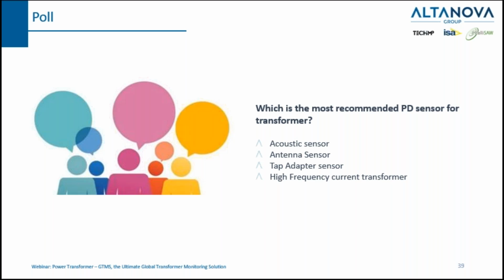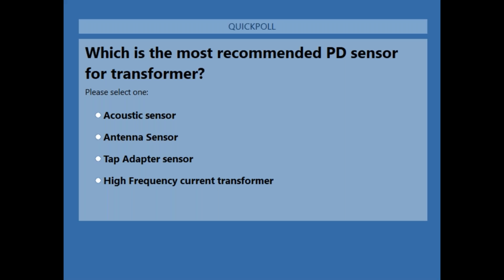Just a quick stop. Here is the third poll for you. It is about which is the most recommended PD sensor for a transformer. Basically, we are asking all of you, in case of a PD test or PD monitoring, whether the most recommended is an acoustic sensor, an antenna sensor, a tap adapter, or a high frequency current transformer.